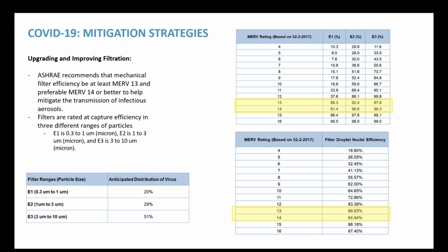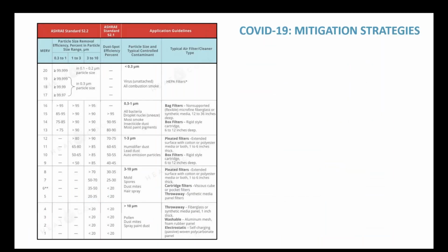And when we're talking about particles that may be suspended in the air, the smaller the particle size, the more likely that is. So it goes back to their idea that airborne transmission is a significant pathway and we need to address it. And so they came up with what they called filter droplet nuclei efficiency. That's taking all of this information, combining it together and saying, MERV 13 is great, you're around 90% efficiency. MERV 14 is even better, it gives you almost 95% efficiency. And that becomes really important when you're doing large air changes within a space and a lot of filtration. At 95% efficiency, you can remove a lot of particles.